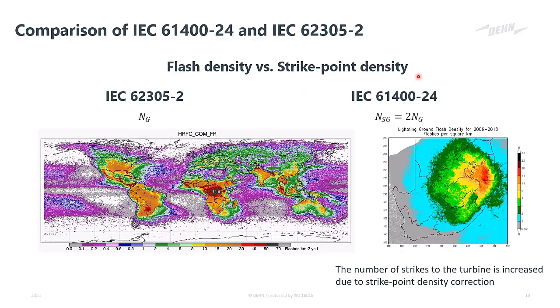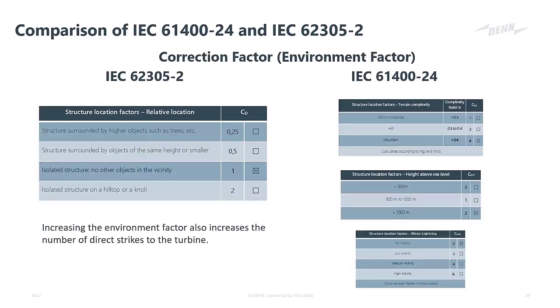Because we said we increased the lightning activity within the area, the standard adjusts the flash density by doubling it. It's multiplied by 2, and then we have a factor for strike point density. I also mentioned that the correction factor is different. So the correction factor, again, is just looking at surrounding objects to see what are the chances of your structure getting struck as opposed to other ones within the area. Now, in 62305, we simply just look at, am I isolated? Is there something else around me that's the same height or smaller? Is there something that's much taller than I am? Or am I isolated on a hilltop or knoll?